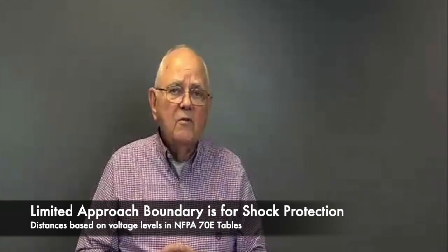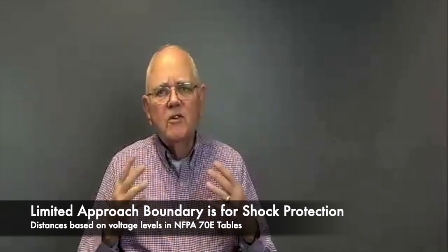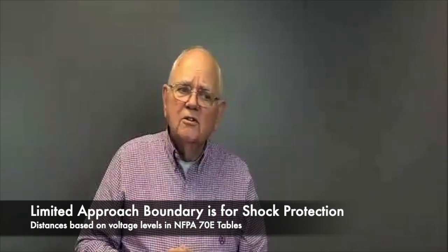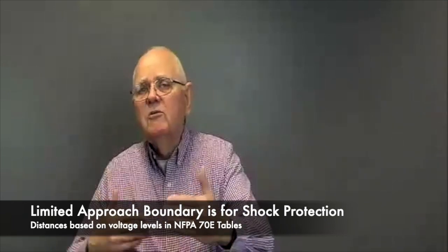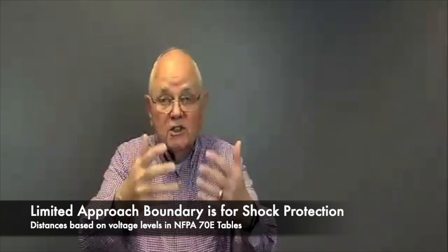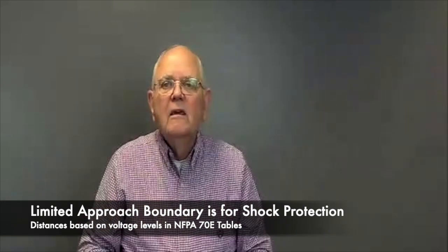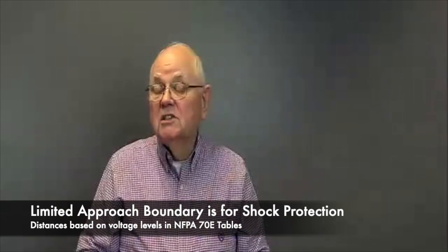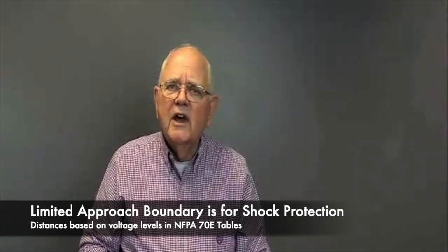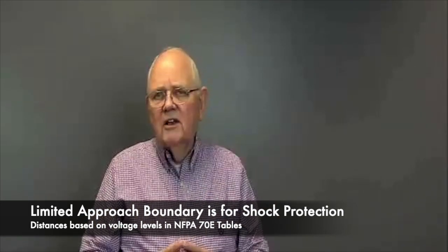As far as fixed circuit parts are concerned, the limited approach boundary for our medium voltage levels on up to 15 kV is going to be 5 feet, 0 inches. And what does 5 feet, 0 inches mean to us? That's the distance that if we get within 5 feet, 0 inches of a live exposed, in other words, the door is open, energized part, is considered to be an area where there's possible shock injury. And so we want to make sure that we keep all unqualified people out of that limited approach area. Now, with one exception, if I've got somebody coming in there to watch me do some work, I can keep them within that limited area as long as they're dressed out appropriately. And then maybe the unqualified person we're attempting to train, but they're not allowed to actually physically do any work.